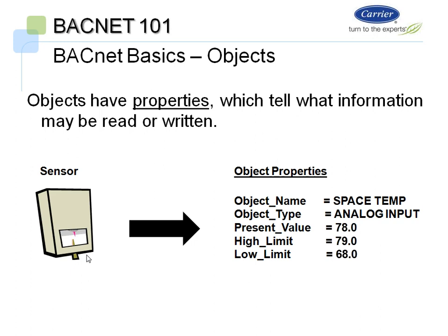So the first property of an object is the object name. This is how you find that object, that point, and how it's represented throughout the system. So for instance, your sensor has an object name of space temp. And that sensor, being a space temperature sensor, is an analog input, which is the object type. And then it also gives you a present value, which is the current reading of that sensor at the time, as well as a high limit and a low limit reading as well.